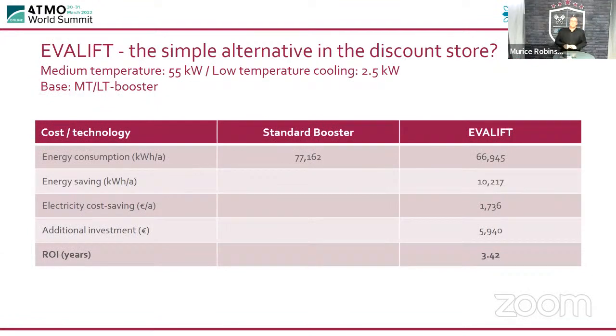So, having a look at some data, I just want to show you the difference. This is a small store with 55 kilowatts of medium temperature and 2.5 kilowatts of low temperature. We compared a standard booster, and we installed the EVALIFT in a store that was very similar. The energy consumption in kilowatt-hours on the standard booster was 77,162, and with EVALIFT it was only 66,945. Now just remember, you're saving on both sides, so it's the low temperature and the medium temperature.